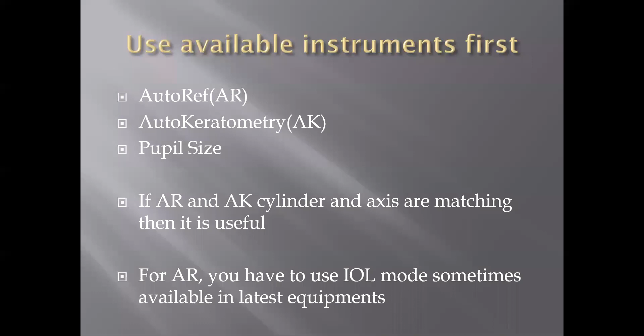And for AR, you have to use IOL mode sometimes available in latest equipments. In some instruments, recently they have added IOL mode. If you are not getting reading on regular mode, then you have to switch over to the IOL mode and click the readings, and that will give you few readings. This is also true with the small size pupil.